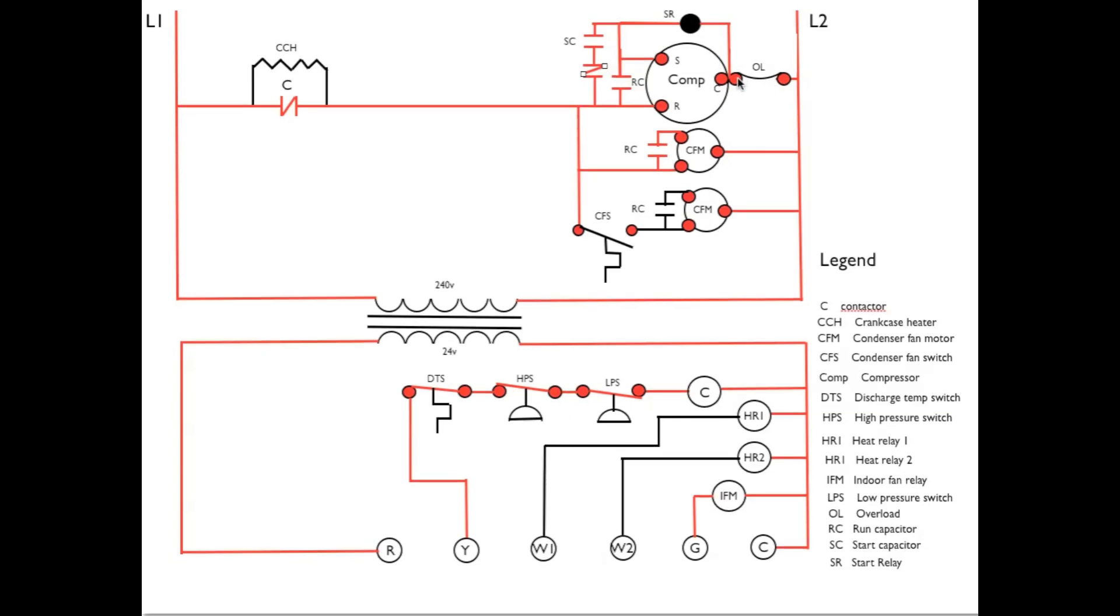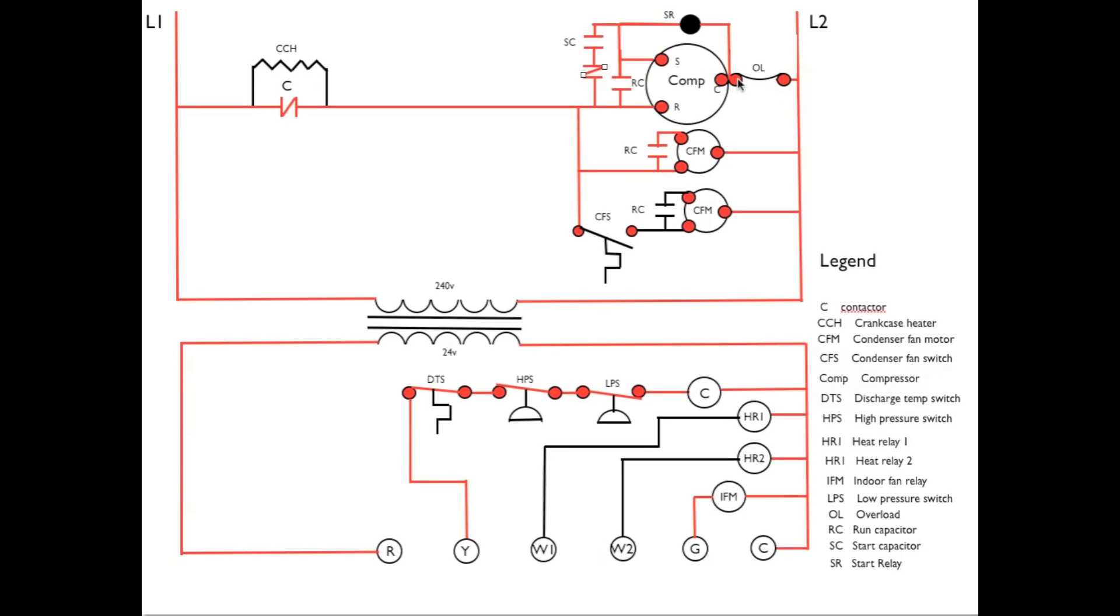which is going to shut down the common side of the compressor, which will shut it completely down, if there is an over temperature in the wiring going from C to L2. That would mean probably an overdraw in the compressor.